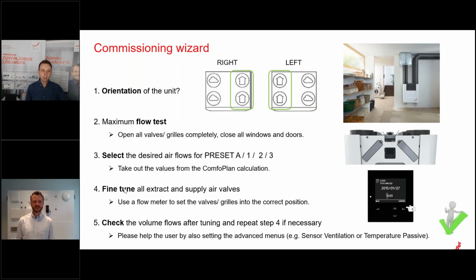Then you need to fine-tune all extract and supply air valves in the apartment. For that, you need to use a measurement device like a flow meter, which will be shown by Tobias from Testo later on. This fine-tuning takes a bit of time, depending on the size of the ventilation system and how experienced you are in adjusting the valves and grills. You won't get perfect results after the first round of adapting, so you need to repeat that step to get an appropriate result. Our Zehnder service technicians typically need two rounds of adapting the valves, so it takes them one to two hours. We will take a closer look at this process on the next slides.